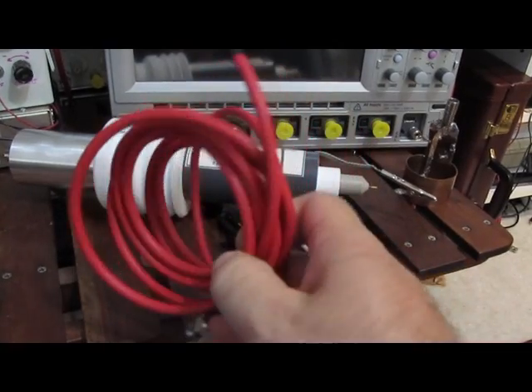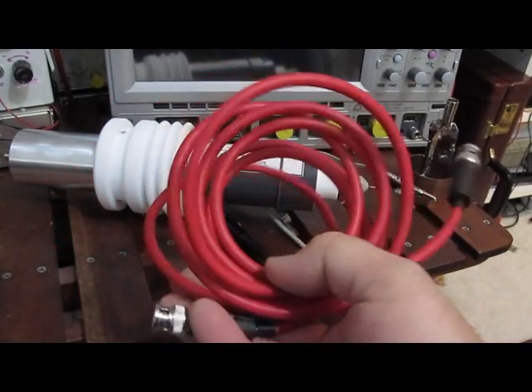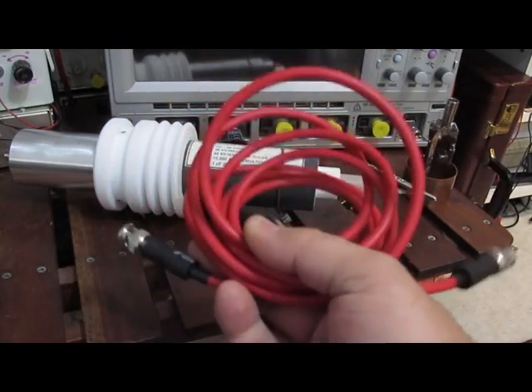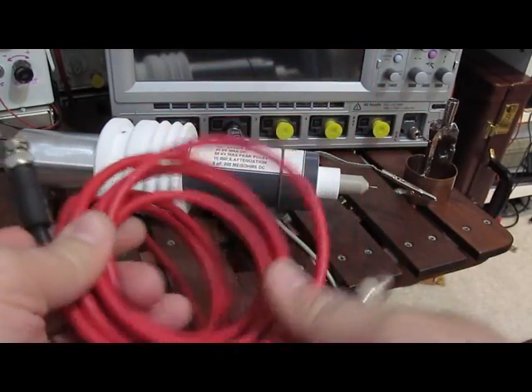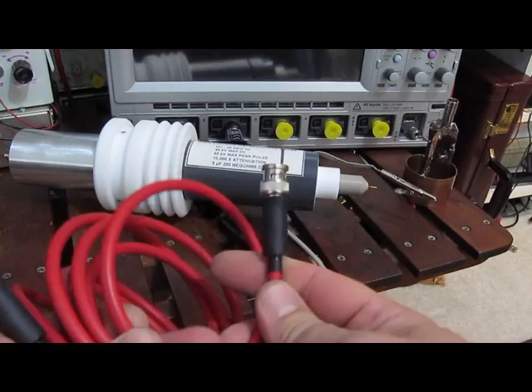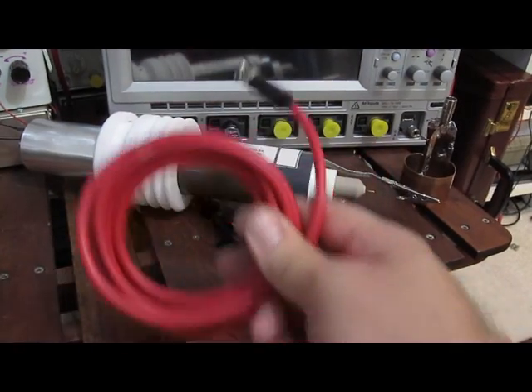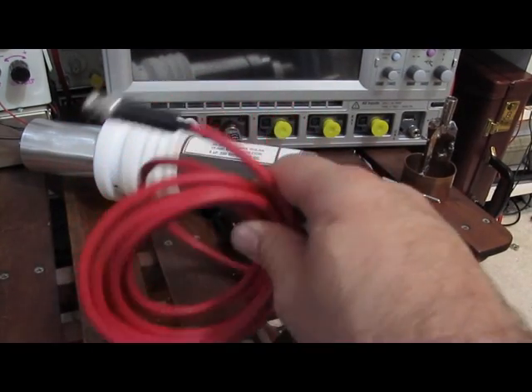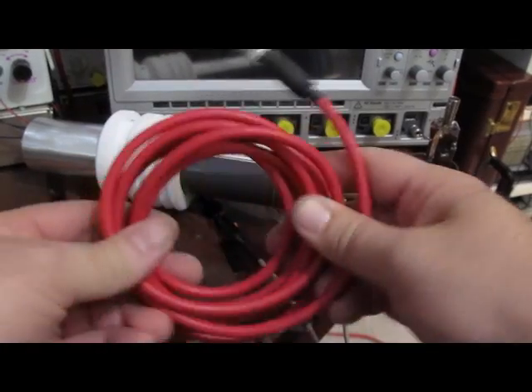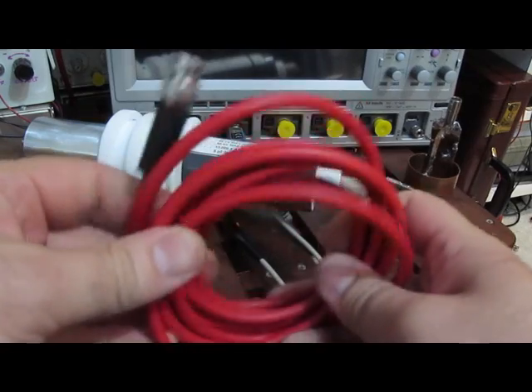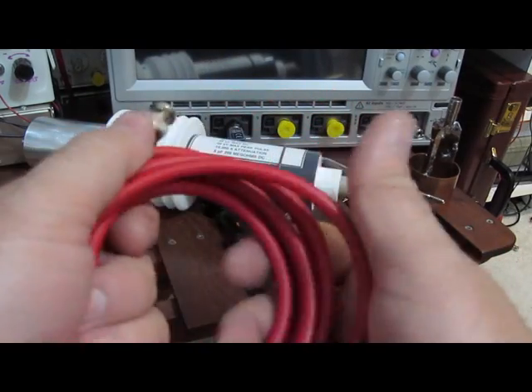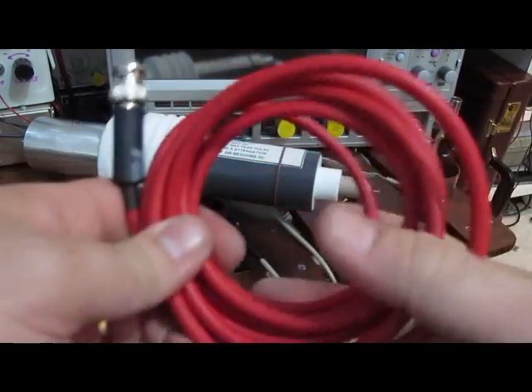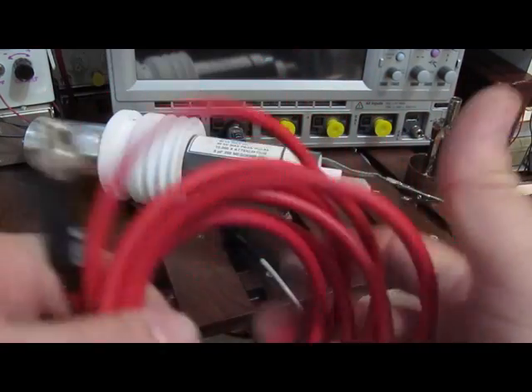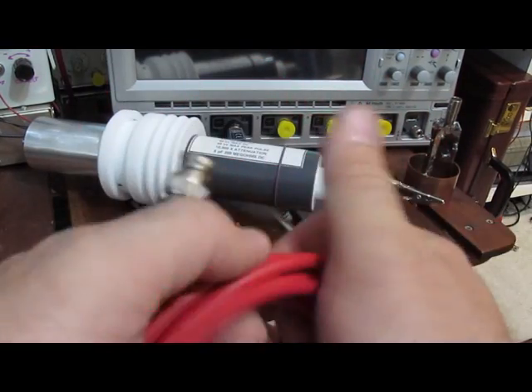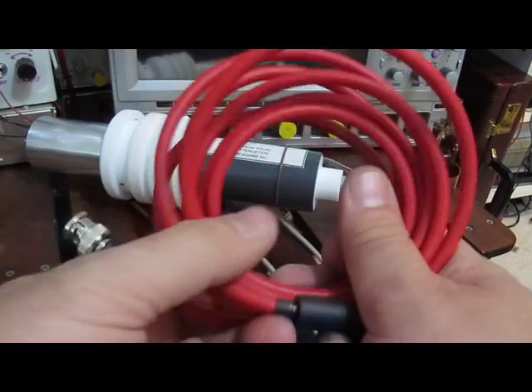This is the cable that is made for the probe. So the probe is actually compensated to work with this cable. So there's no compensation at the end of the cable, it just plugs directly into the oscilloscope. So changing out the cable length here would require the probe to be retuned. It's optimized for this cable length right now. I ended up with about 8 foot of cable total, and that's just basically because I was looking for better fidelity. 8 feet is pretty long. I didn't want all the excess cable normally bundled up to keep it out of the way.